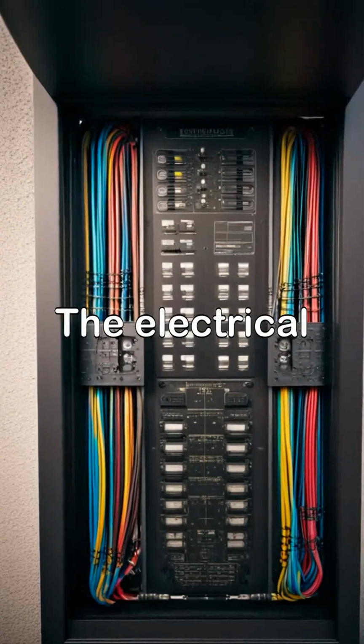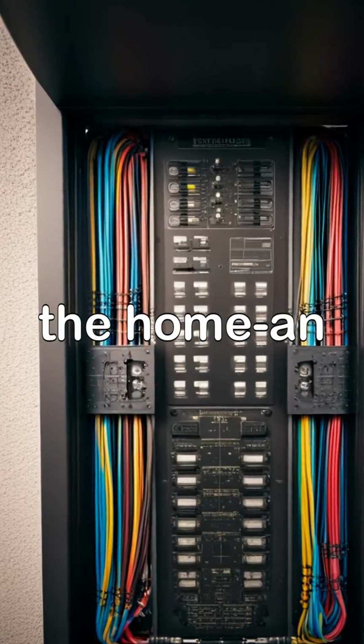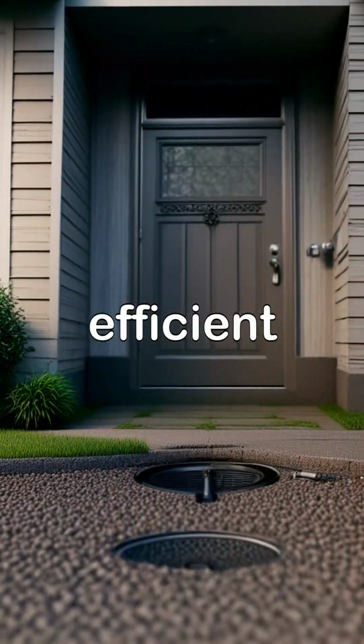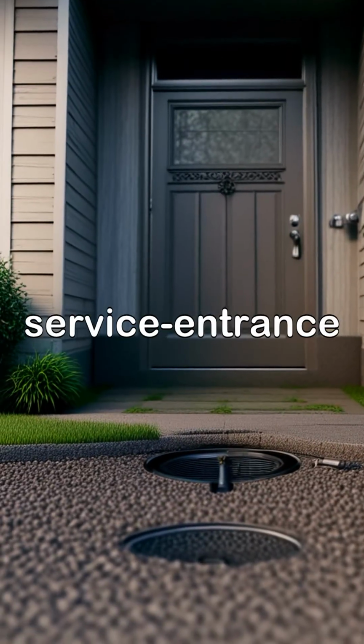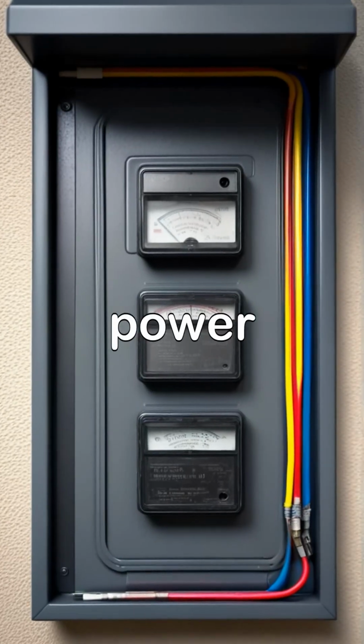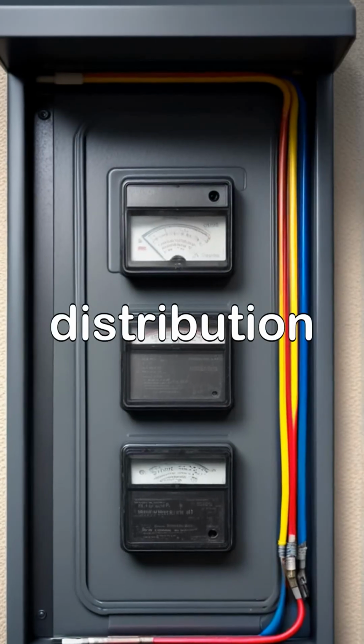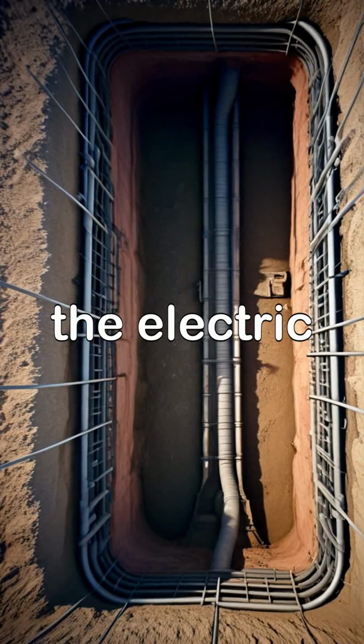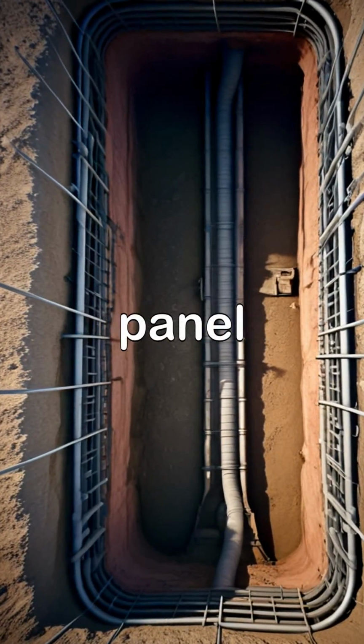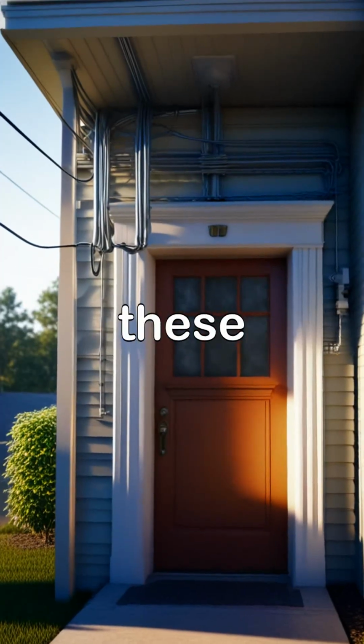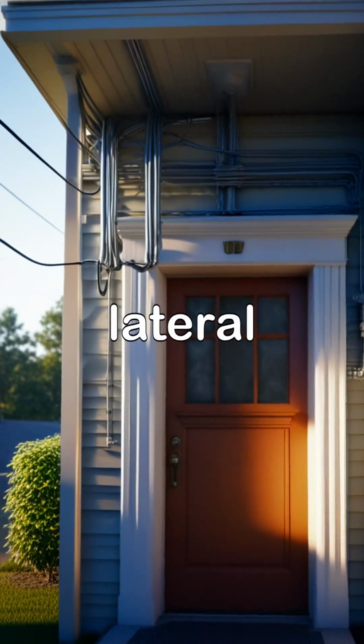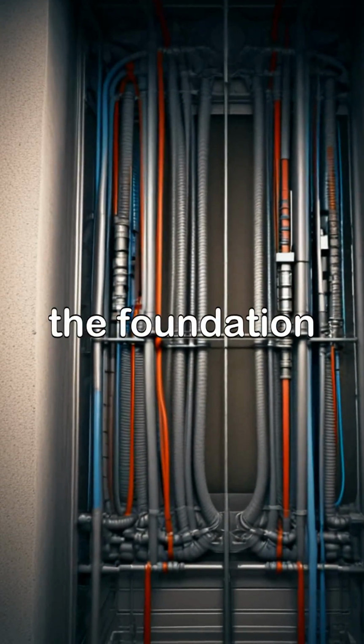The service entrance. The electrical distribution system within the home, an intricate but logical and efficient system, is centered in the home's service entrance panel. 3 wires bring power from the 120-volt side of the distribution transformer through the electric meter and then into the service entrance panel. If the house has underground service, these wires, called the service lateral, rise through the entrance conduit that comes out of the ground alongside the foundation.